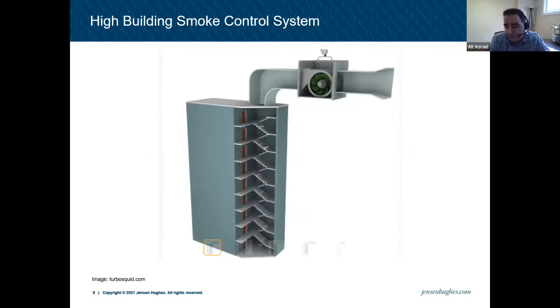This is an example, an image of a fan and a stair shaft. The fan is pressurizing the stairs. So technically, if there is smoke, it cannot get into this stair from the floor area. This area is pressurized, the smoke tries to get in, but the pressurized air is not going to let the smoke get into the stair. And it keeps it safe for occupants to evacuate the building.